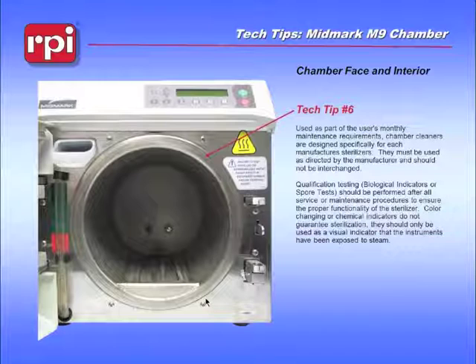As part of the monthly maintenance, you need to clean the machine. You should be doing qualification testing, spore testing, with runs to be sure that the operator is not overloading the machine or choosing the wrong cycle for what they're putting in the machine, to ensure that not only did the machine function properly, but all of the material within the sterilizer is sterile.